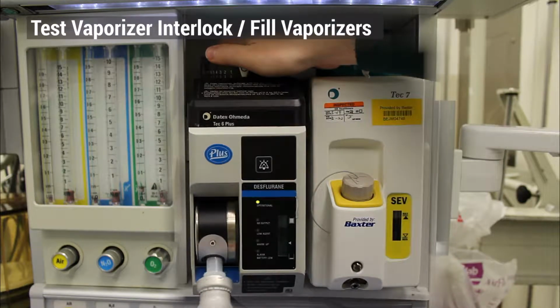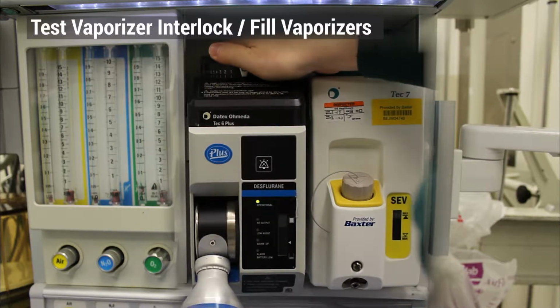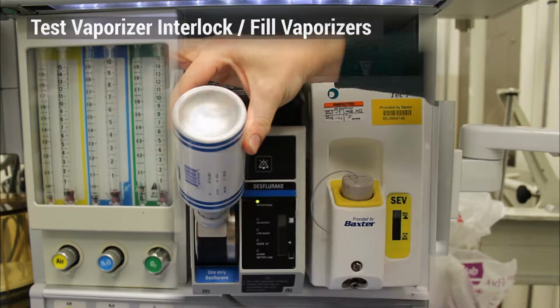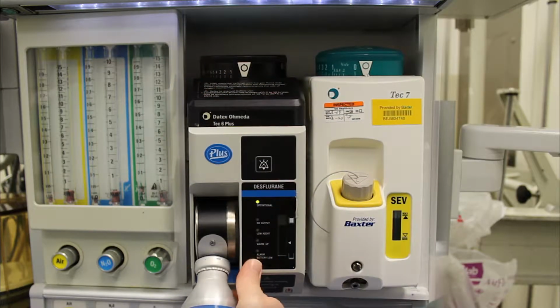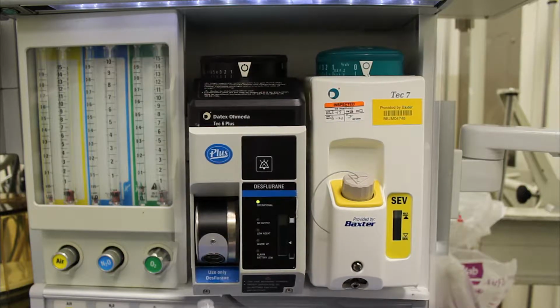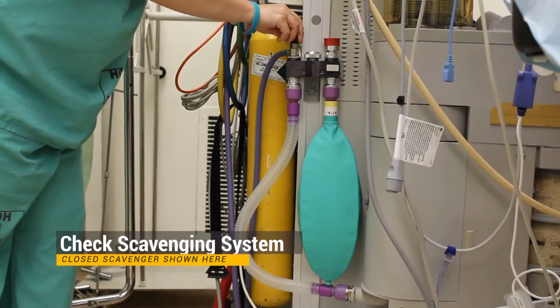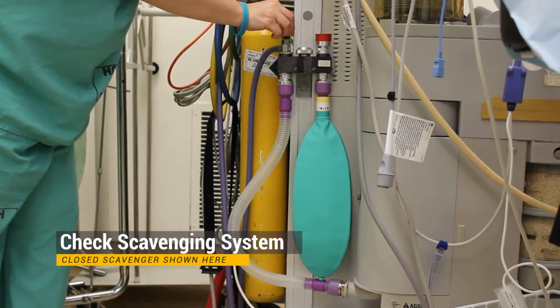Verify that only one vaporizer will turn on at a time and that they are filled and the filler ports are fully closed. The Tec 6 Plus does not have a fill cap, as shown here. Test that the scavenging system is functional and the suction set properly.